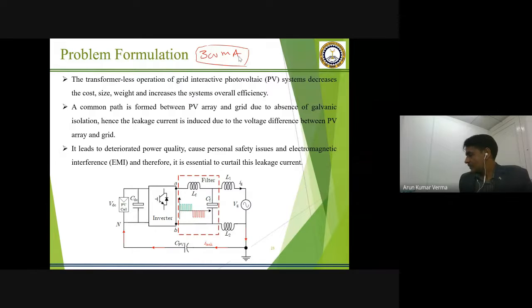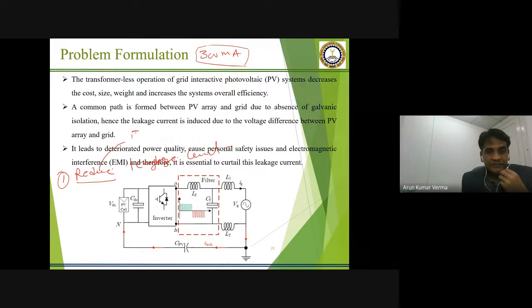Now, this leakage current leads to deteriorated power quality, causes personal safety issues, already I have told, and electromagnetic interference, that is EMI, and therefore it is essential to curtail this leakage current. So the first target of our work is to reduce leakage current. Or better to use the word eliminate. Eliminate leakage current. So in a few topologies, we can eliminate the leakage current. Eliminate means zero leakage current. Okay. But in a few topologies, we can't eliminate it. We can only reduce it.